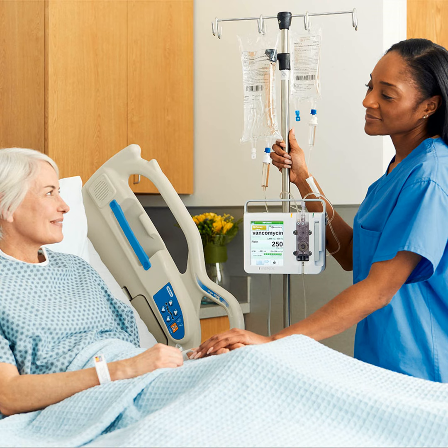Or if you fail to unclamp the secondary tubing, you'll have the delivery of the primary bag instead of the secondary bag. Who hasn't done that? If you hang the bags at the same level, you may have concurrent flow. And then when you do that, it's at a very unpredictable rate. And then finally, there can be residual medication left in that secondary IV bag. Sometimes 20, maybe 30% of that really critical antibiotic is left in the bag, often resulting in an underdose. So how many nurses listening to this webinar have encountered these issues? And I would presume the majority have. And again, less than 5% of nurses understand why you need to hang bags in this manner for those linear peristaltic pumps.